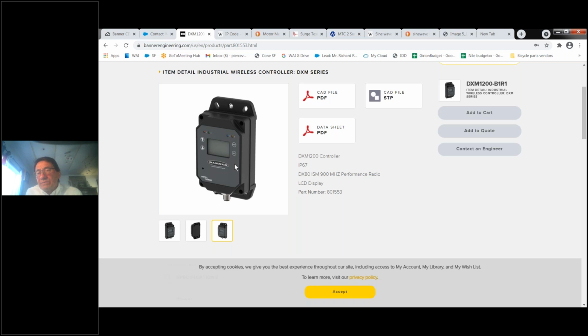You put a chip into this device and it has a cell phone link to the internet. You set the transmission rate, typically collecting all the data and pushing it up once every 5, 10, or 30 minutes. It doesn't need to be every second since this is a pumping application, not a lot changes from second to second, but you want to see what's going on in the field. There are also trending parts of the graphical user interface that give you a trend over time.